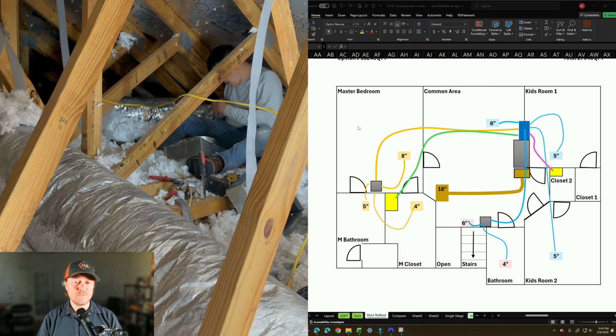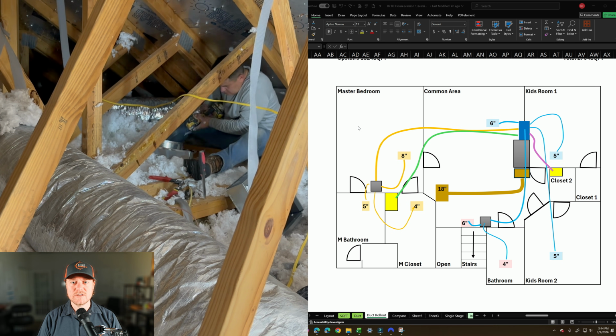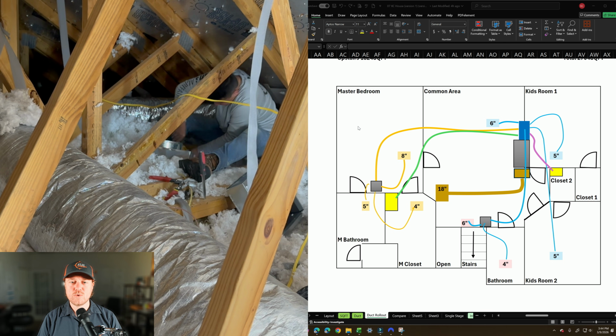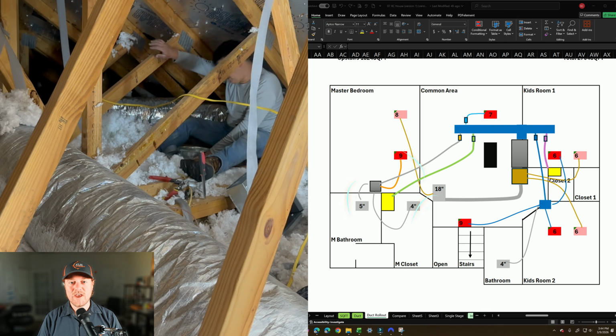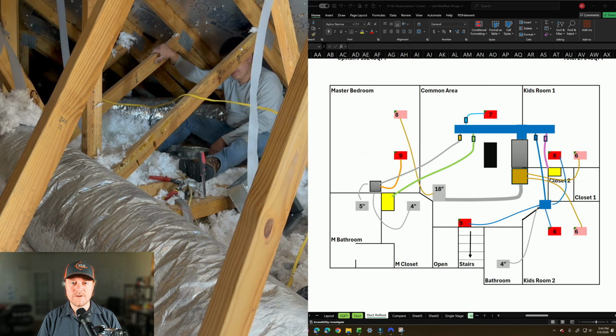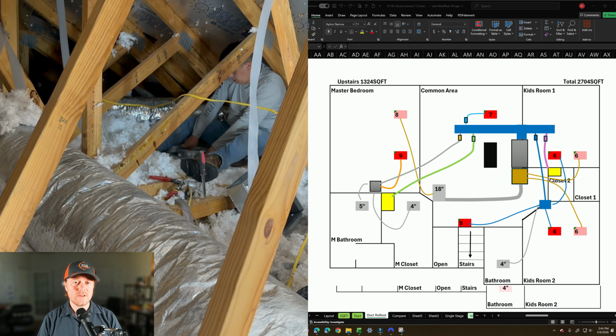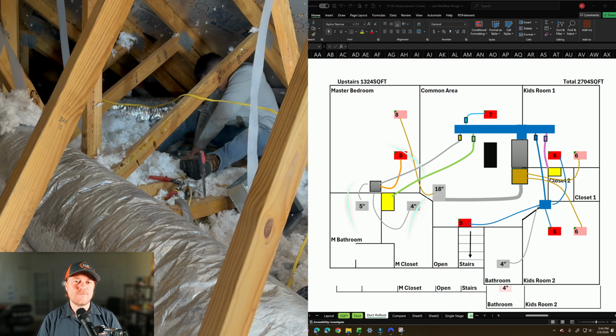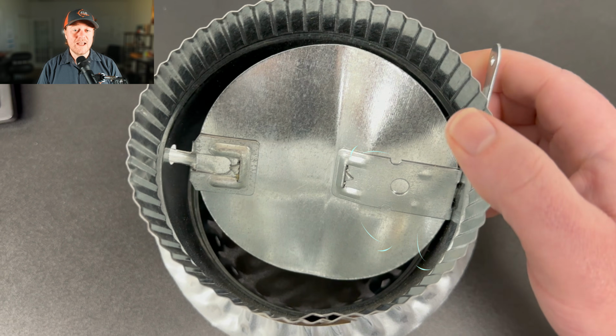And the reason for this is because the last system had undersized ductwork, and it created a lot more pressure throughout all the ductwork, and it was trying to push air wherever it could. Now that we have properly sized ductwork, there's not as much pressure throughout the ductwork, and the air is no longer trying to force its way out wherever it can. And that's what's causing this.